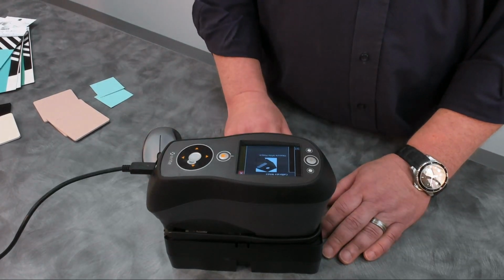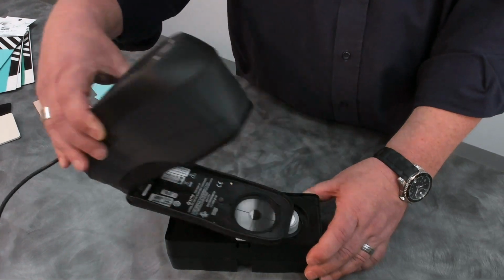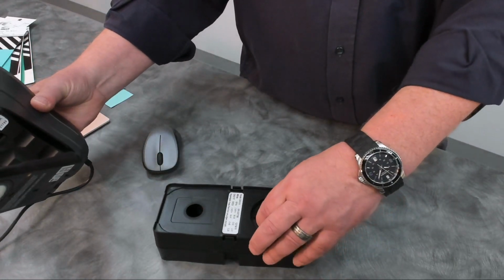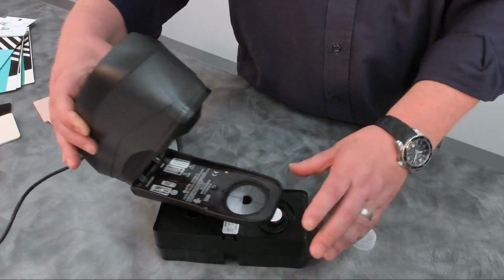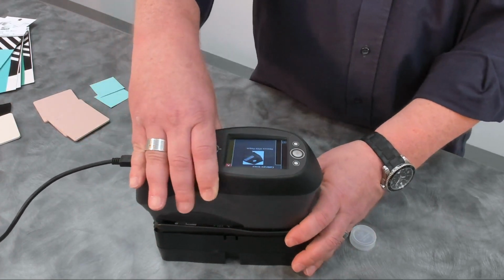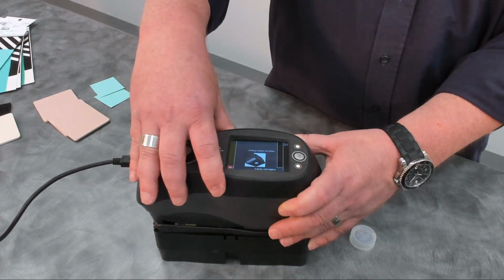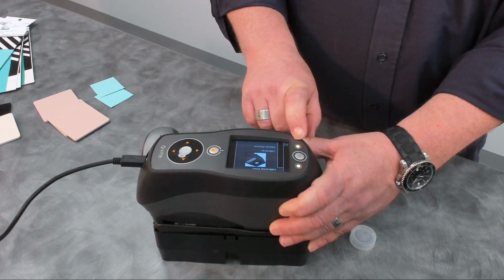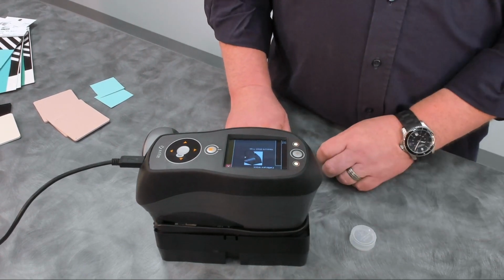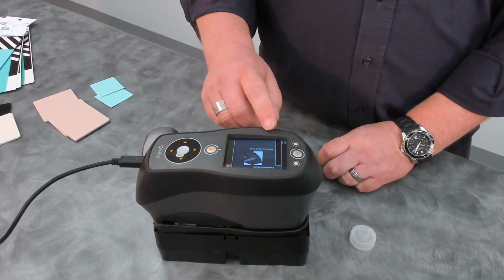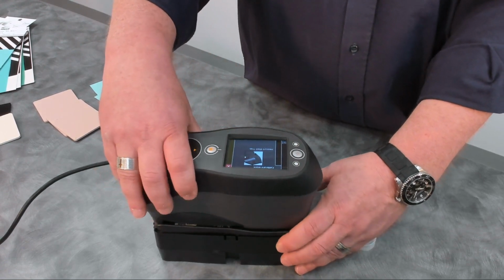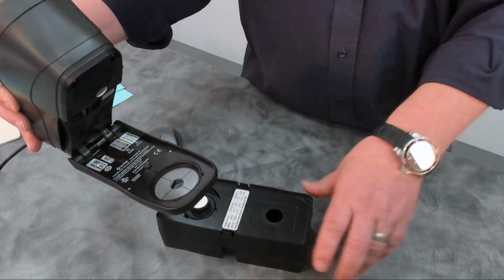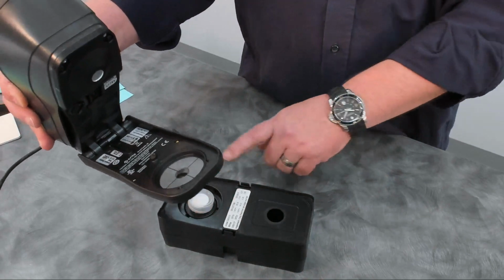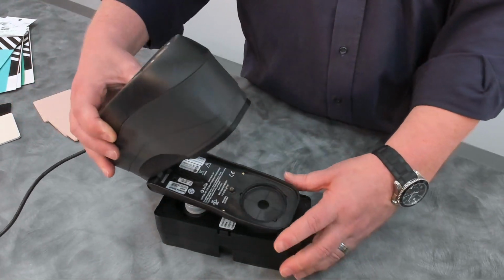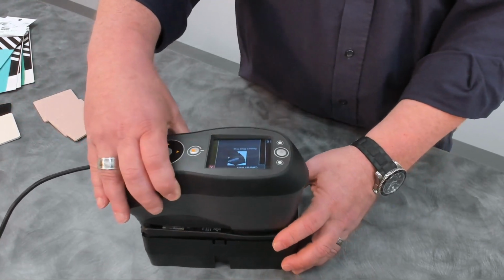And it says measure white plaque. So the calibration standard has a white plaque. I remove its protective cover, place the instrument on top, press down. The lights indicate that it's measuring the calibration plaque. The beep means that it was successful. And now the instrument says measure black trap. So I'm going to rotate this, put the cover back on so I don't damage my plaque, and now measure what's called a light trap.